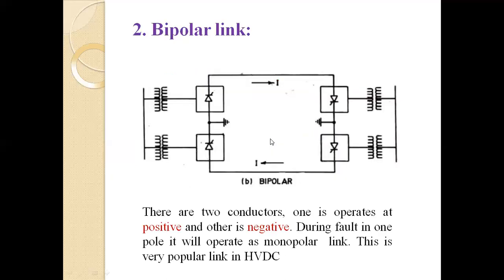Second is the bipolar link. So here the bipolar link is present. Here is the source. There is a transformer, whether it is a step-up transformer or a step-down transformer. At the sending end, we use the step-up transformer, but at the receiving end, we use the step-down transformer. Here a converter is provided for every line. For this line, one converter is provided, and for this line, one converter is provided. Similarly, at the receiving end, two converters are provided, one for the first line and one for the second line. Here, this point is grounded.